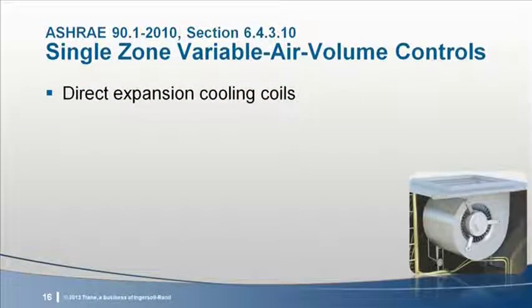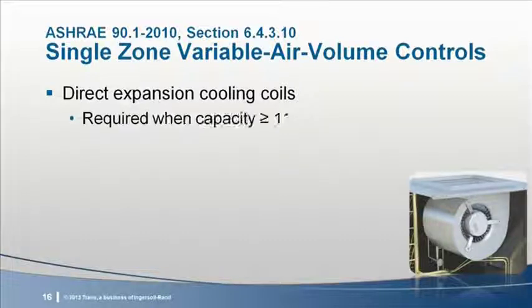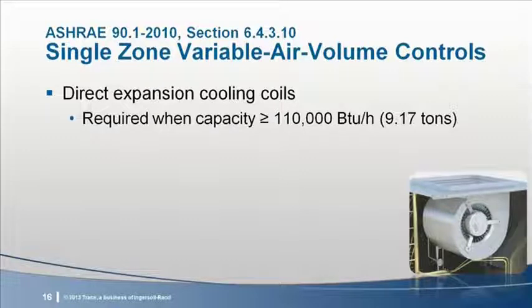Part B addresses systems that use direct expansion for cooling. For equipment with DX cooling, the standard requires variable airflow controls if cooling capacity is 110,000 BTUs or larger. This equates to just over 9 tons. Note that in an effort to make this simpler to enforce, the size threshold is based on the capacity at the ASHRAE standard rating conditions, not actual capacity at the given application. Standard rating conditions can be found within the established test procedure for specific equipment.